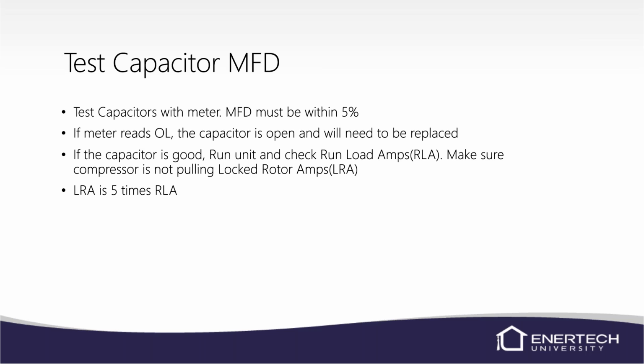Make sure the compressor is not pulling lock rotor amps. We do list lock rotor amps in our manuals, and it's usually 5 times what the run load amps are, so it's normally somewhere around 125 amps. On some meters you can't really read it because it's really quick. I've got a meter that will read it and hold the inrush on there. Sometimes you have to have a special meter, or you have to look really quick because it won't last long.